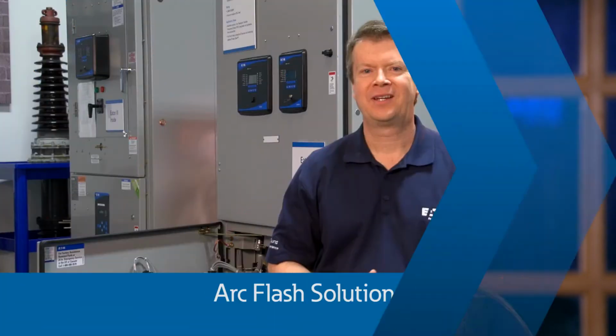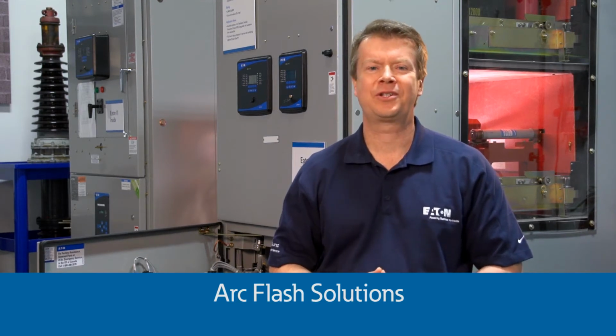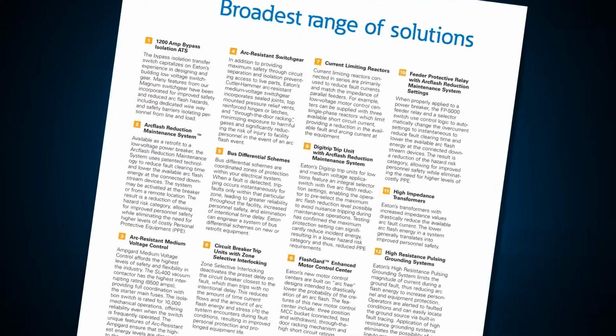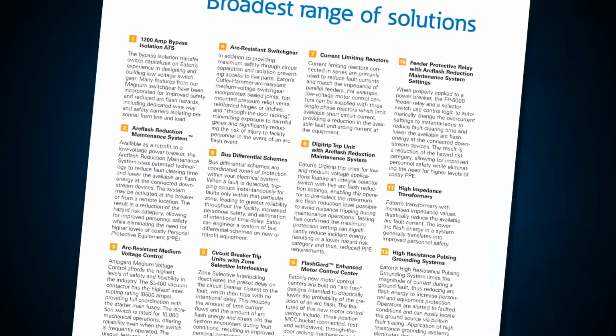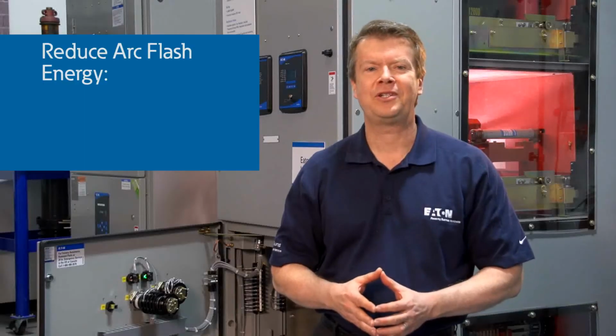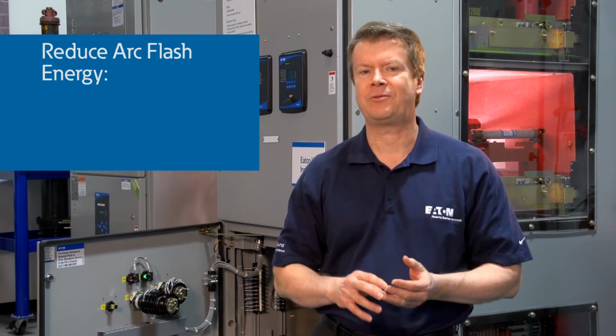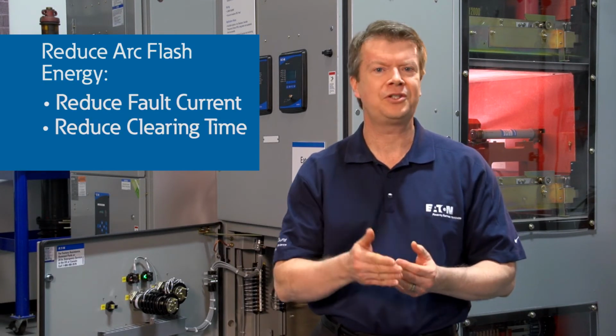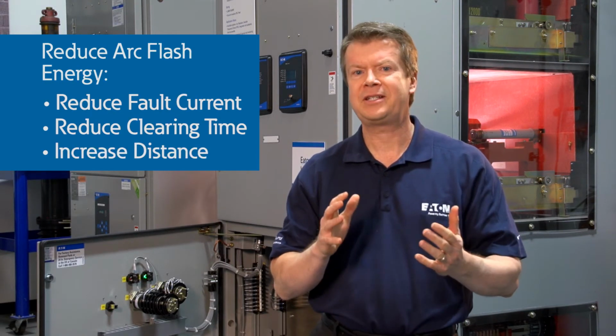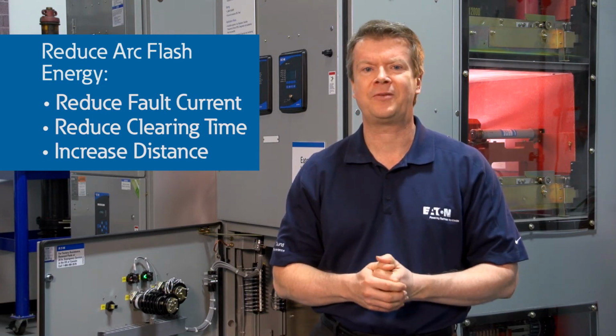safety. Eaton has nearly 100 solutions for arc flash safety. And here at the Power Systems Experience Center, we can introduce you to all of them. We focus on opportunities to reduce the arc flash energy by reducing the fault current, reducing the clearing time, and increasing the distance from the arcing fault to personnel.